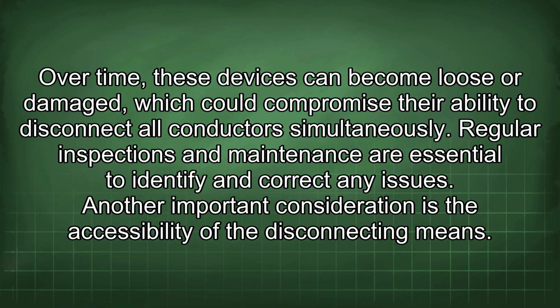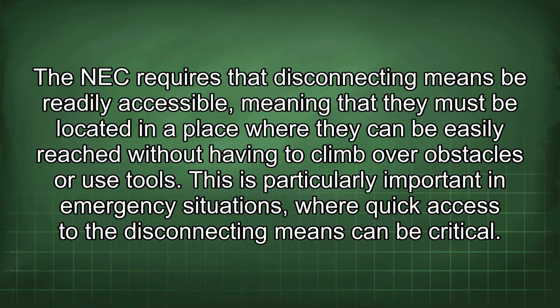Another important consideration is the accessibility of the disconnecting means. The NEC requires that disconnecting means be readily accessible, meaning that they must be located in a place where they can be easily reached without having to climb over obstacles or use tools. This is particularly important in emergency situations, where quick access to the disconnecting means can be critical.